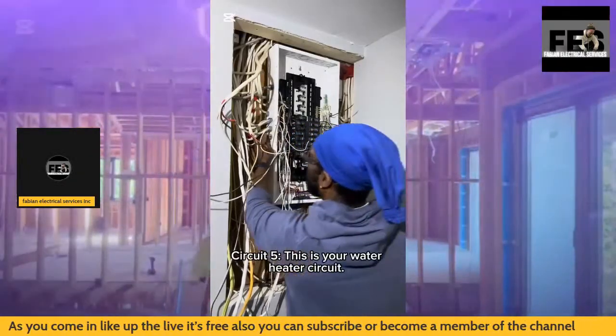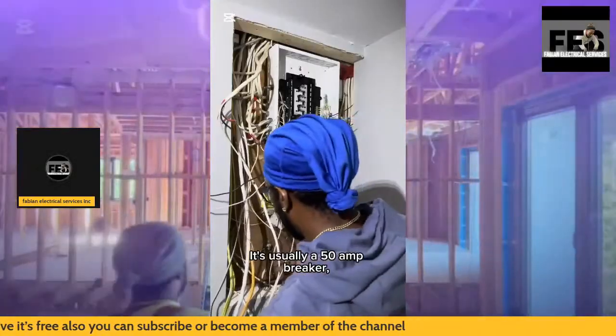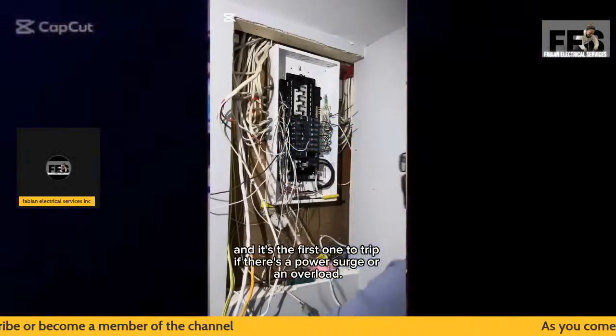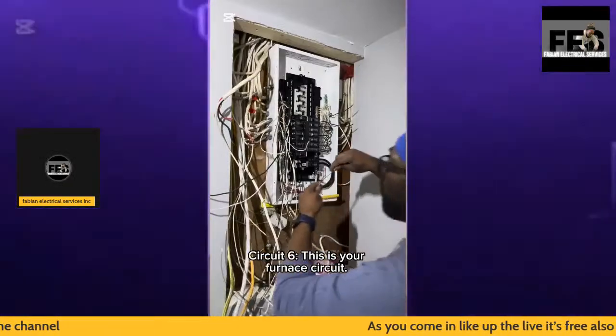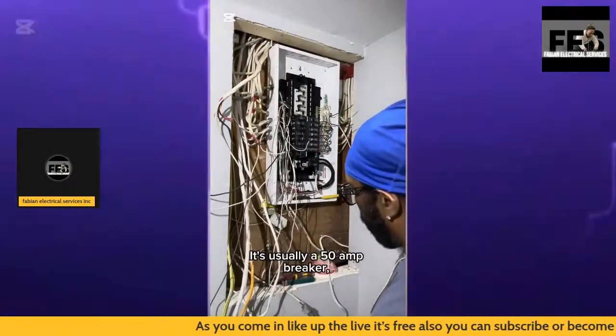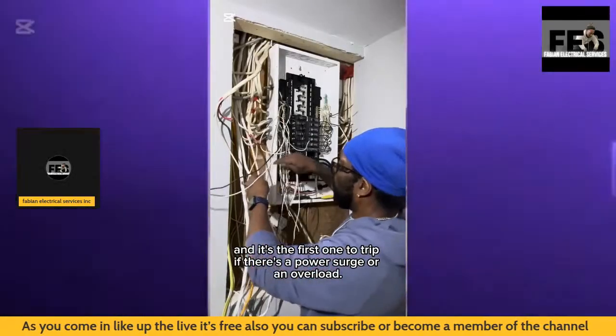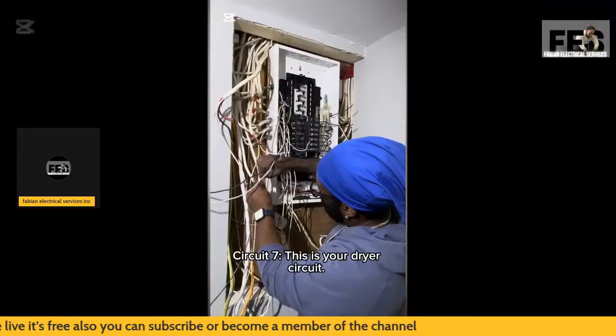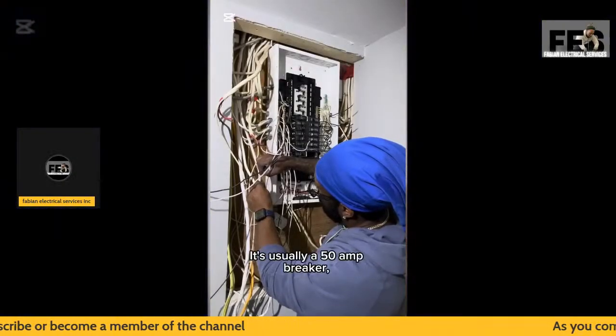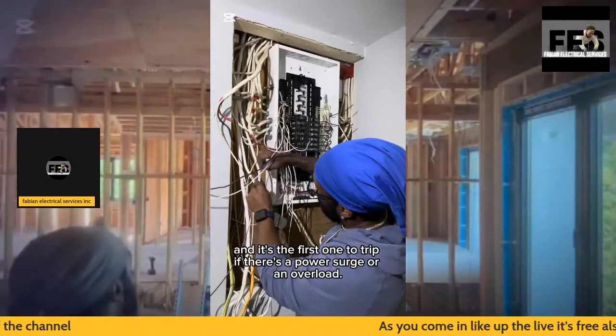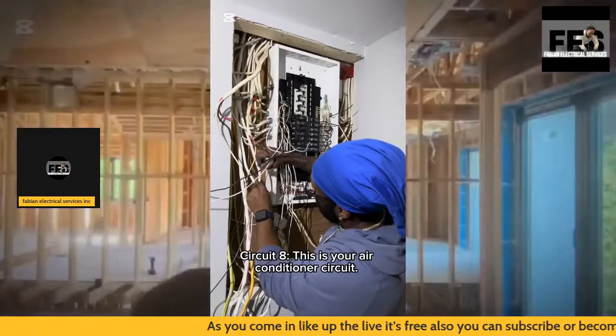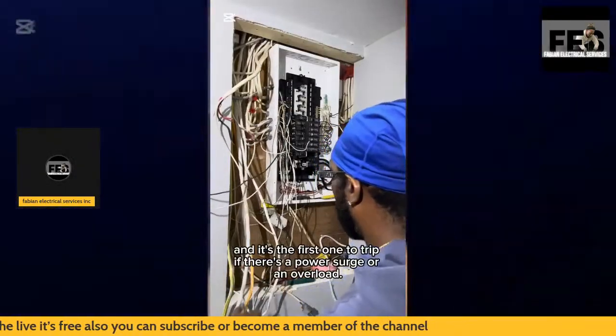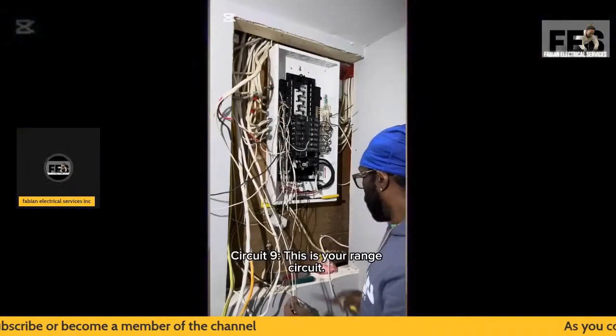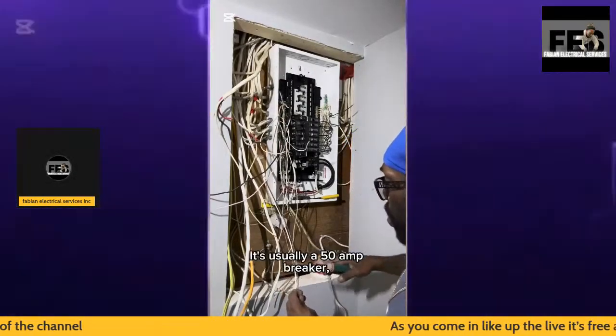So what we have here is a panel change out. I know it's a little tight here, but I had no room to play with - it was basically framed out before I did the service. The reason the panel is the way it is right now is because the service is coming from the bottom, and I couldn't flip this panel the other way because there's obviously a code rule on that - there's an actual height that your breaker is supposed to be within. It wouldn't pass inspection if I had flipped it into the wrong position.